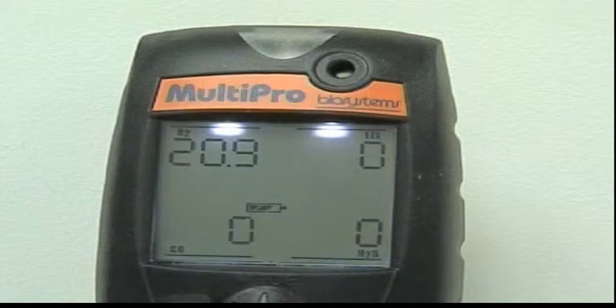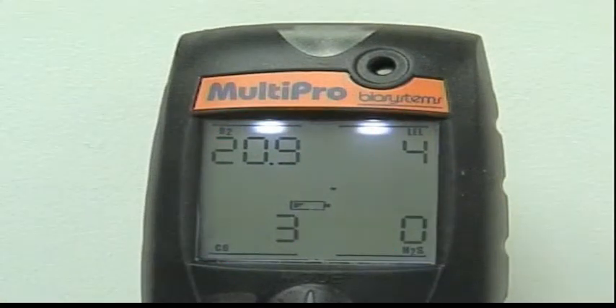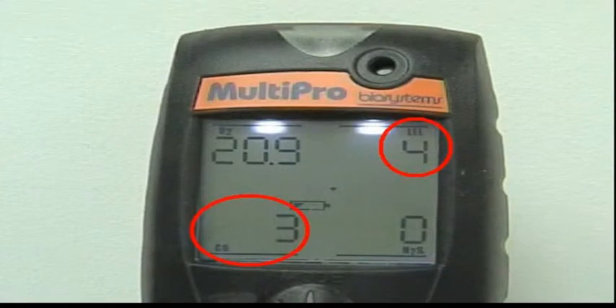The oxygen reading should be 20.9%, and the LEL and toxic sensors should read 0. If the instrument shows readings other than 20.9% for oxygen and 0 for the LEL and toxic sensors, the instrument should be fresh air or 0 calibrated before proceeding with the bump test.